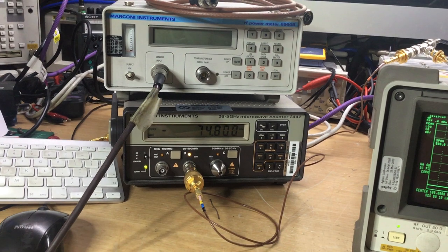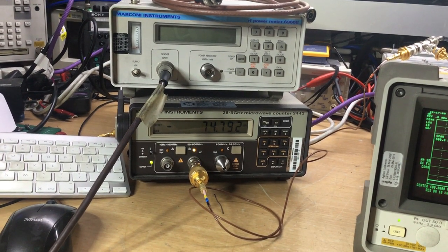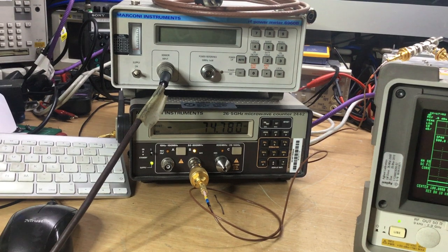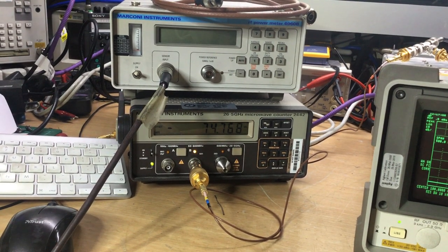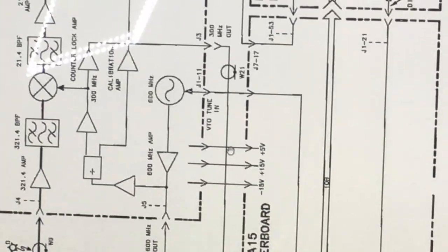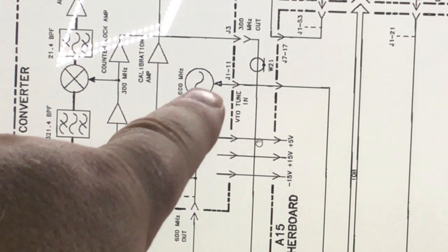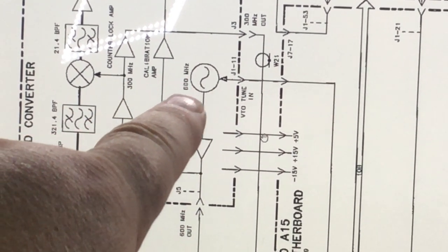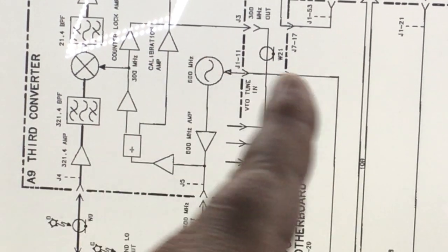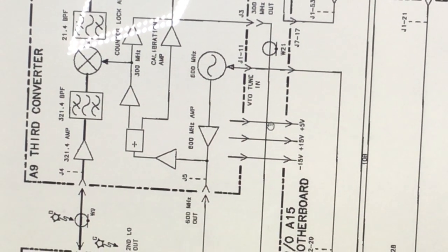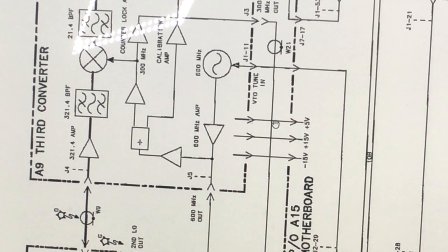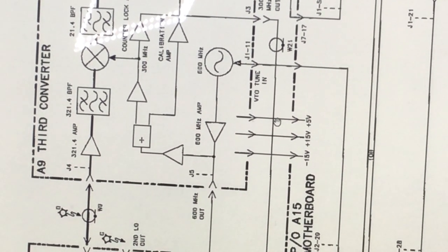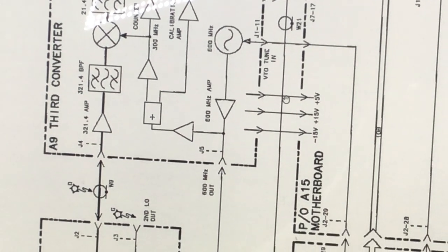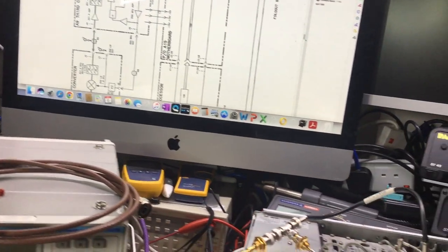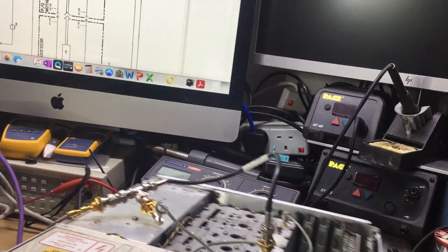So there is a frequency adjust available on the third converter, which we can use to alter the 600 megahertz output frequency. It influences the VTO line here on the 600 megahertz. It controls that 600 megahertz oscillator to adjust its frequency slightly, and we might be able at this point, where we're measuring now, to recover that frequency accuracy. And there's a potentiometer in the third converter that you access through the top, which I'm going to show you in a moment, but basically that's how it works.